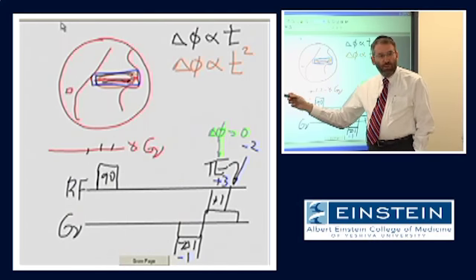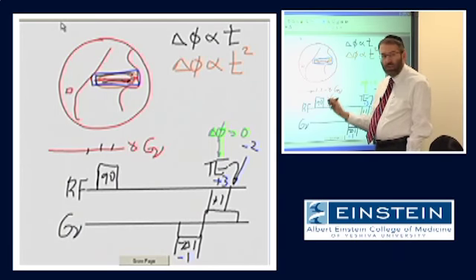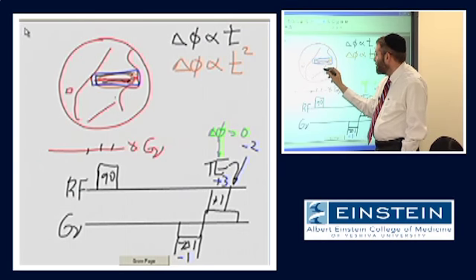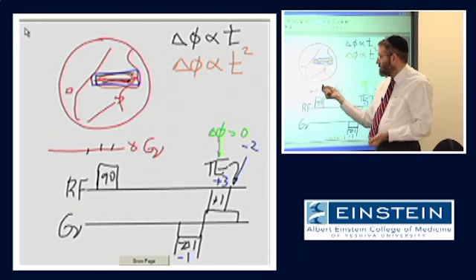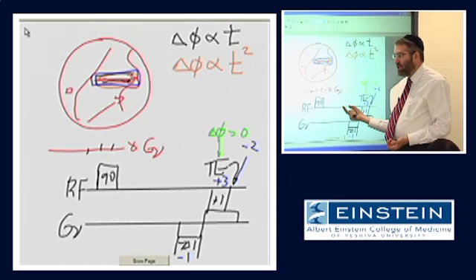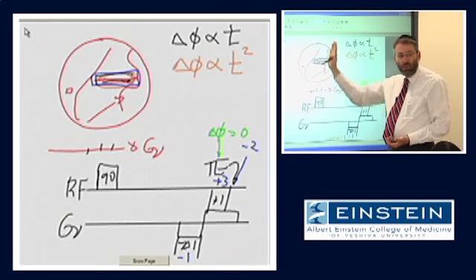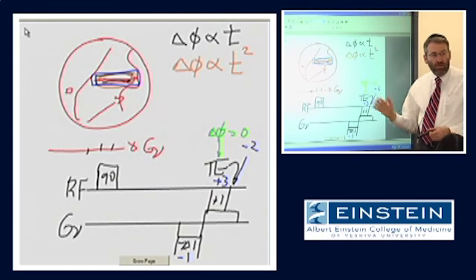This could be along the frequency encoding gradient — I made a very simple example here — or equally along the phase encoding gradient. And of course, flow is never perfectly parallel to the gradient magnetic field. Even if our flow direction looks oblique, we essentially have two components of flow since flow velocity is a vector. The component along the frequency encoding gradient will undergo this phase shift based on the frequency encoding gradient, and the component along the phase encoding gradient will undergo phase shifts based on the phase encoding gradient.